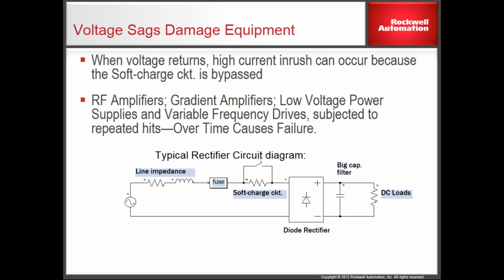There's another aspect to this, and it's the one that causes real damage, the one we see when drives have shorter life or power supplies are destroyed, sometimes looking like we got hit by lightning. The front end of the power supply, the diode rectifier circuit, is burned right up, and people say we must have gotten hit by lightning. No, lightning might have hit, but it hit down the road, and what you experienced came at the end of the voltage sag that the lightning caused. Here's why.